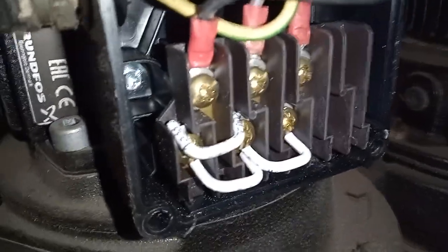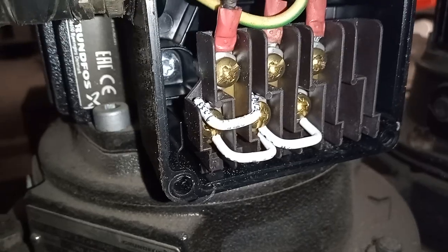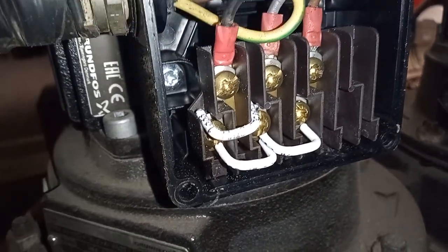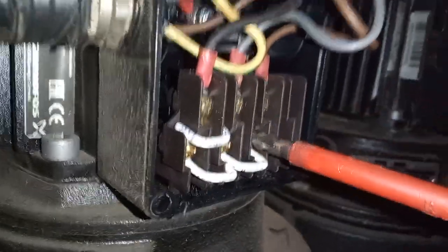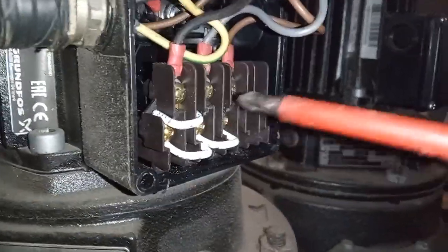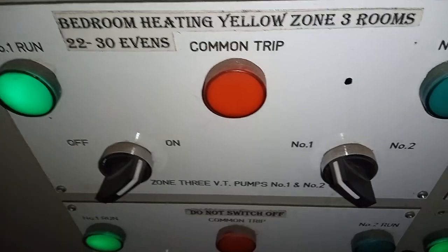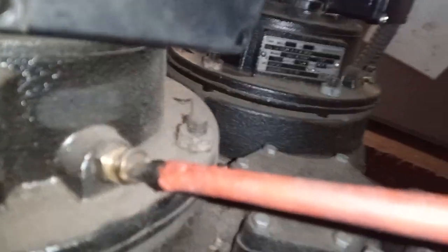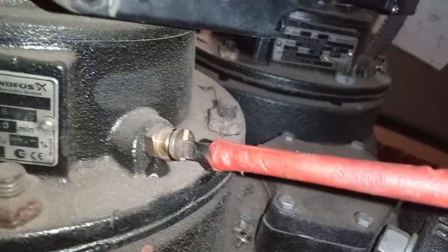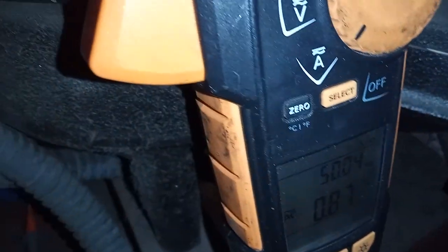I've been checking my connections, tightening them up and making sure they're all the way home and not on a short thread. The connections look pretty good to me. I'm going to vent my pump — I've temporarily put the case back on. Okay, checking my amps again.